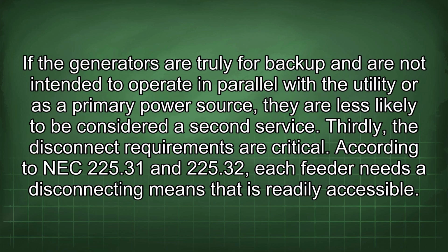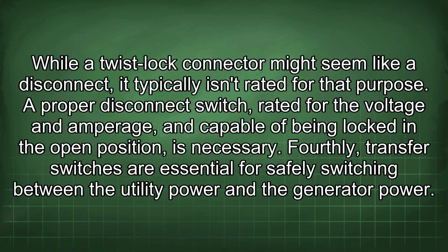If the generators are truly for backup and are not intended to operate in parallel with the utility or as a primary power source, they are less likely to be considered a second service. Thirdly, the disconnect requirements are critical. According to NEC 225.31 and 225.32, each feeder needs a disconnecting means that is readily accessible. While a twist lock connector might seem like a disconnect, it typically isn't rated for that purpose. A proper disconnect switch, rated for the voltage and amperage, and capable of being locked in the open position, is necessary.